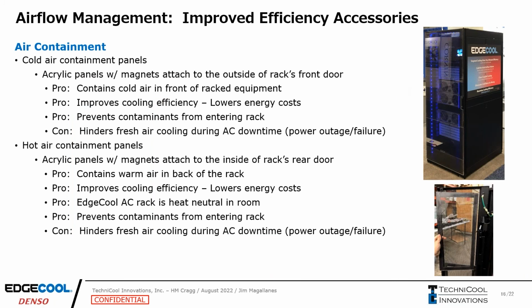Airflow management: we have some accessories that customers can use to actually improve the efficiency of the EdgeCool unit. Cold air containment panels. As you can see here, we have some acrylic panels on the front side of the unit, and that's keeping that cold air trapped inside there. This is a typical datacom rack with perforated doors, and we're keeping that cold air sealed inside there. It improves the efficiency, lowers the energy costs, and prevents contaminants from entering the rack. The only con is it's hindering fresh air from entering during a power outage or a failure somewhere, so you physically have to remove those panels.